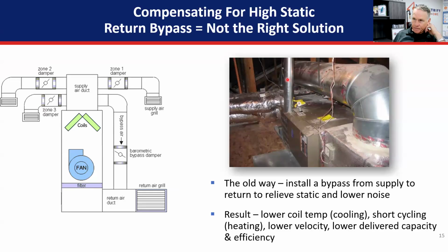A company I worked at back years ago did tons of zoning systems with single stage units and put these bypass dampers in. It was all the choices we had before two stage was a thing. We'd sell a zone system on an existing single stage system, and then we got to put dampers on everything, and put this thing in. All this is doing is letting the conditioned air return back to the return plenum. The systems are not designed to do that.